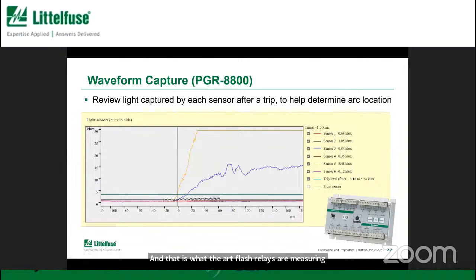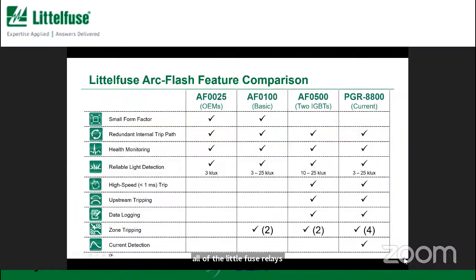So these relays, one other function I'll mention about all of the Littelfuse relays, the AF100, 500, and 8800 have quite a flexible, adjustable light level. So based on how much ambient light you might have, you can adjust the sensitivity of these relays, whether you want them to be very sensitive or to be less sensitive. Now, don't worry, no matter what the setting is, you're never going to miss a real arc, because a typical arc flash would be measured in the hundreds of thousands or millions of lux. And here the maximum setting we allow is 25,000 lux.